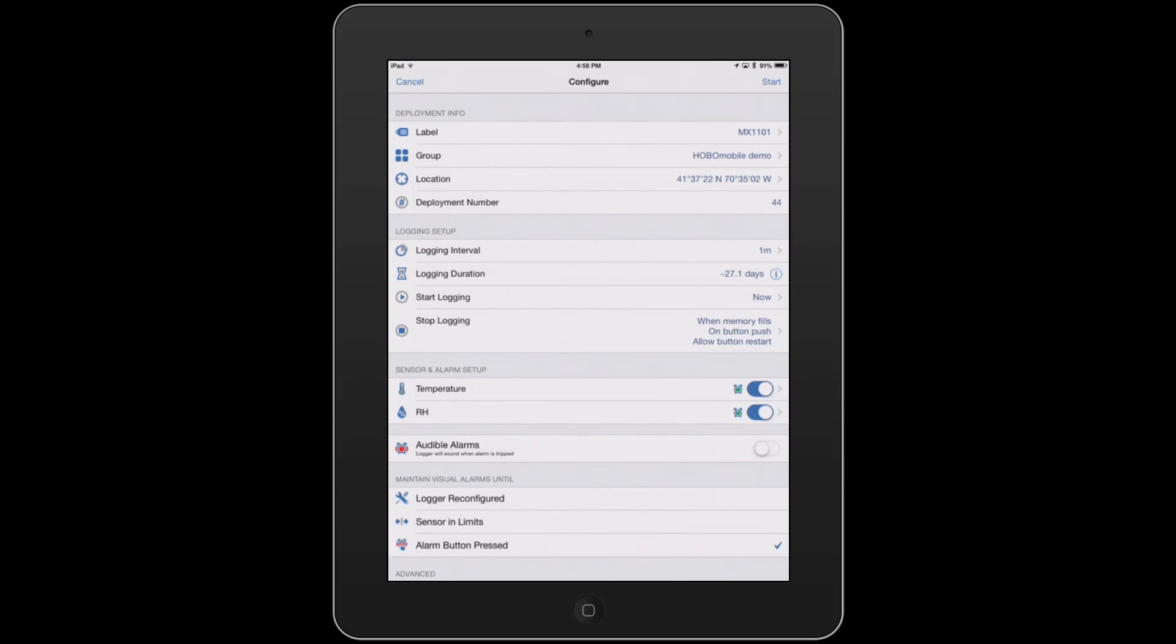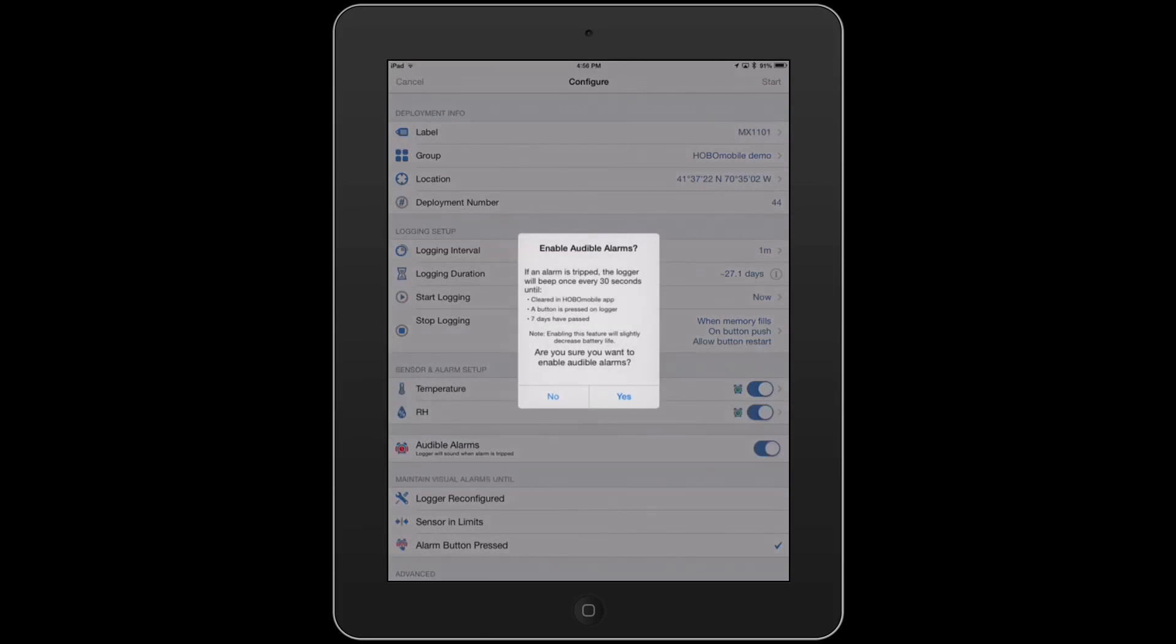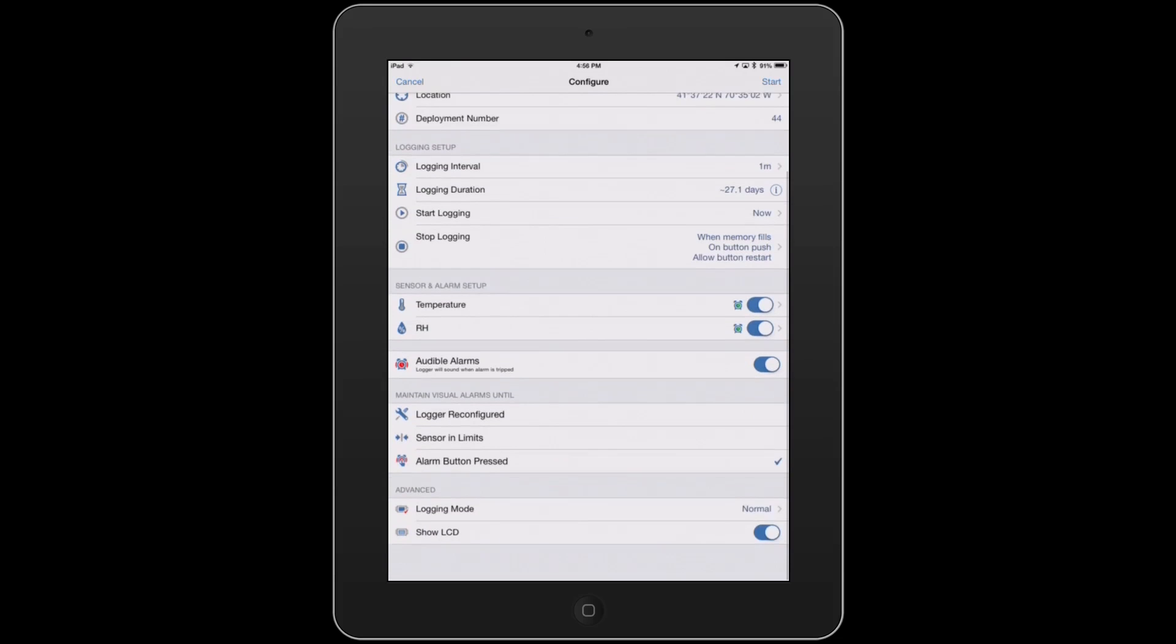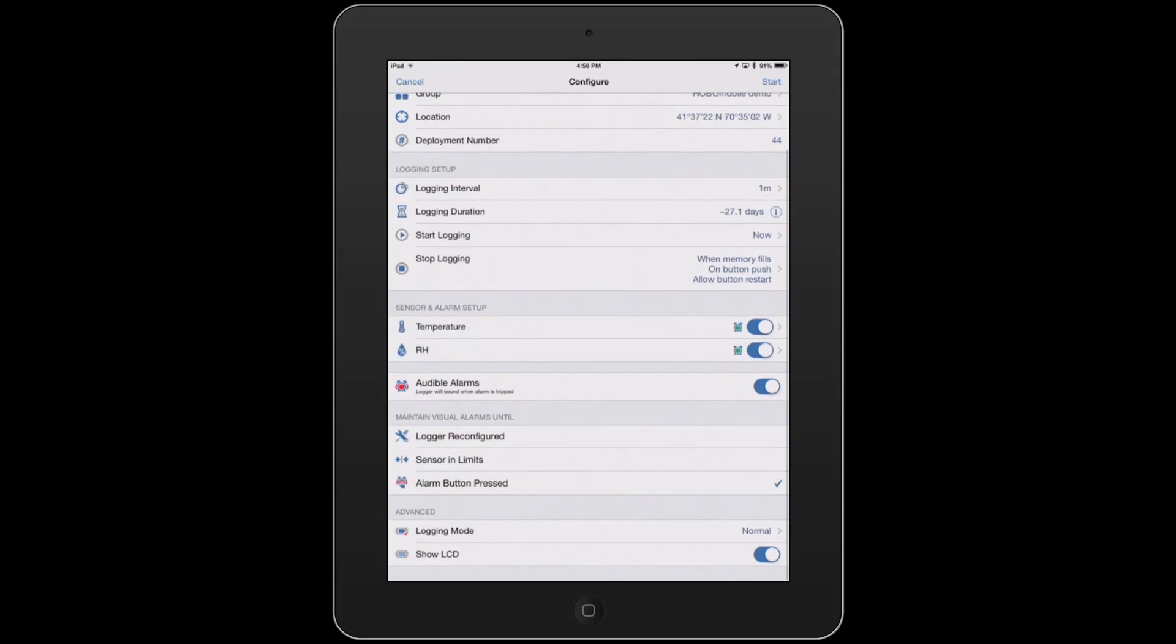You can also have this set up so an audible alarm will happen. So we can turn this on here, and it's going to prompt you that this will beep every 30 seconds once it goes outside of range. And finally, how do you want to maintain the visual alarms, whether it's by a button press, or if the sensor comes back in the limits.